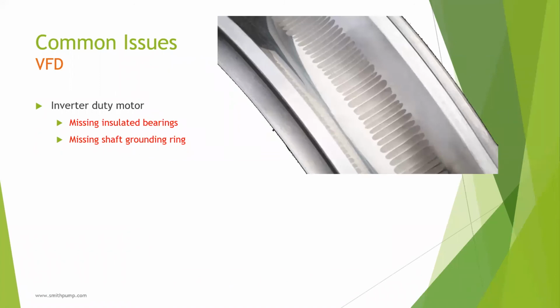As VFD popularity grew, so did the problems. Smith Pump found out the hard way how damaging a VFD can be on motor bearings. You can see the damage that occurred on the bearing races while operating a standard motor on a VFD. Essentially, a charge will build up on the rotor until it can't hold any more charge, and it finds a path to ground. Typically, bearings are the easiest path to ground. So the electrical discharge generates a fluting pattern seen on the bearing race. I don't understand the theory on why this happens, but I do know how to protect motors from this damage.